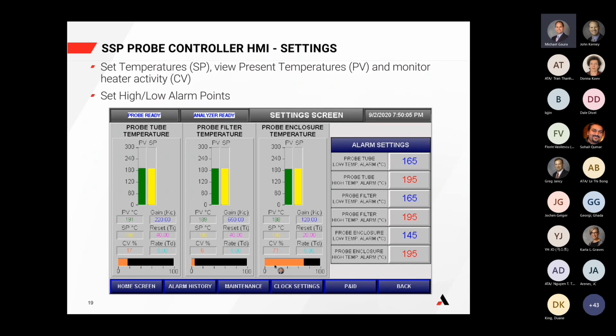Users can also adjust the alarm settings for all three of those locations. For the probe tube, a low temperature alarm can be set as well as a high temperature alarm. Rod talked earlier about 170 C being the dew point for the vast number of applications that we see in these types of applications. But maybe for the end user in this application, we had done some calculations and it looked like the dew point would be a little bit lower, maybe typically around 160 or 155. So the end user, just giving themselves a little bit of wiggle room, is setting that low temperature alarm at 165 to kind of catch it before it really becomes an issue for them.